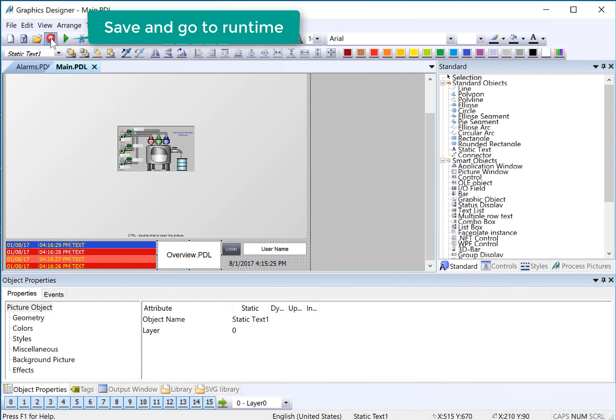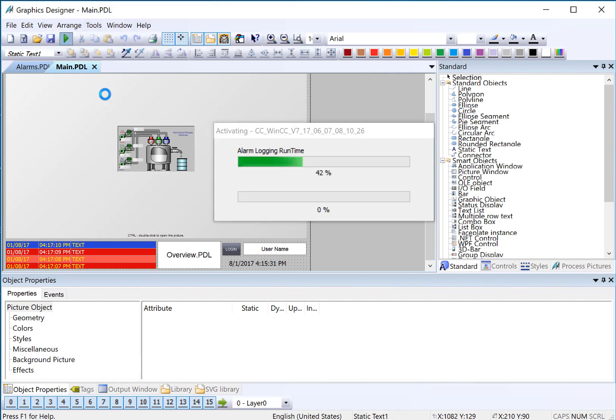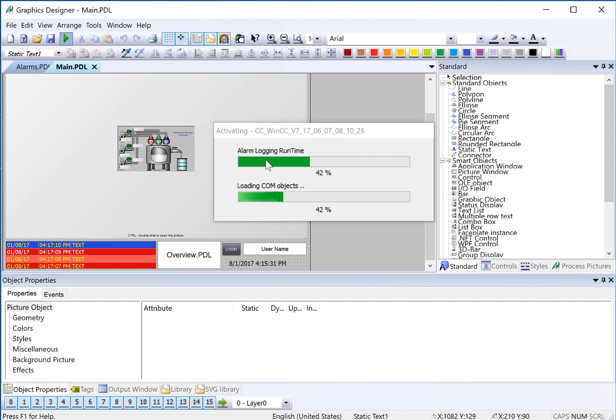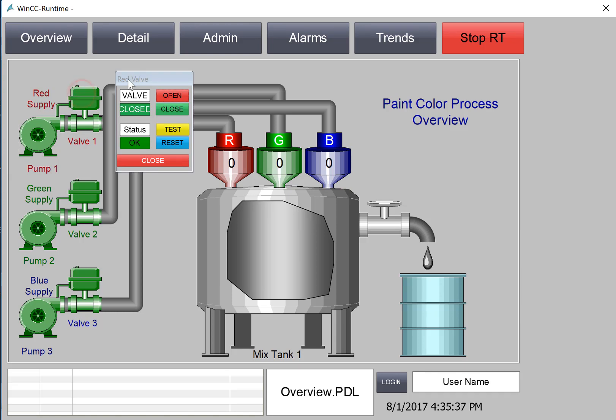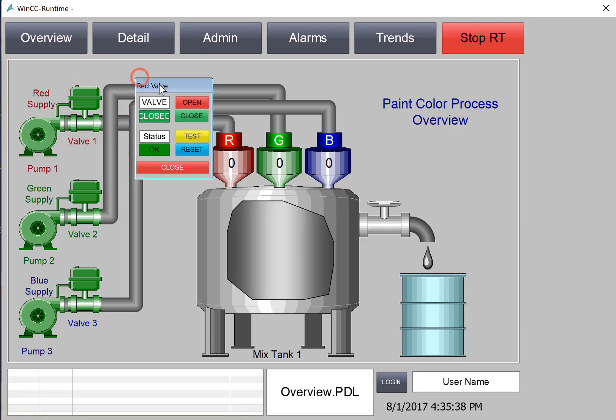And then we'll just go to Runtime to test. And when we're going to Runtime, you should see the Alarm Logging Runtime Editor being activated. And this is because we turned it on in WinCC Explorer. In Runtime, we can test our pump and valve fail alarms by using our pop-up controls.